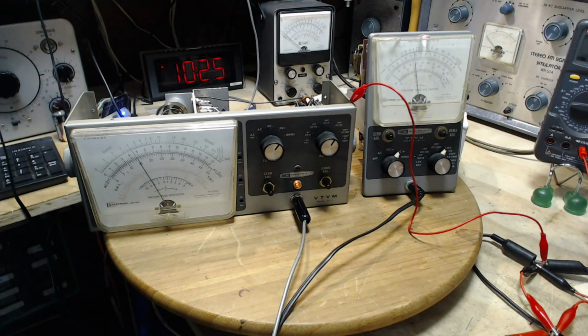But that's what it said it did. It's to allow you to make DC measurements without disturbing the AC voltages. And this buck-out thing is to remove a residual reading on AC that will sit when there's no voltage applied, the meter will read upscale ever so slightly. So this bucking thing is done to eliminate that.